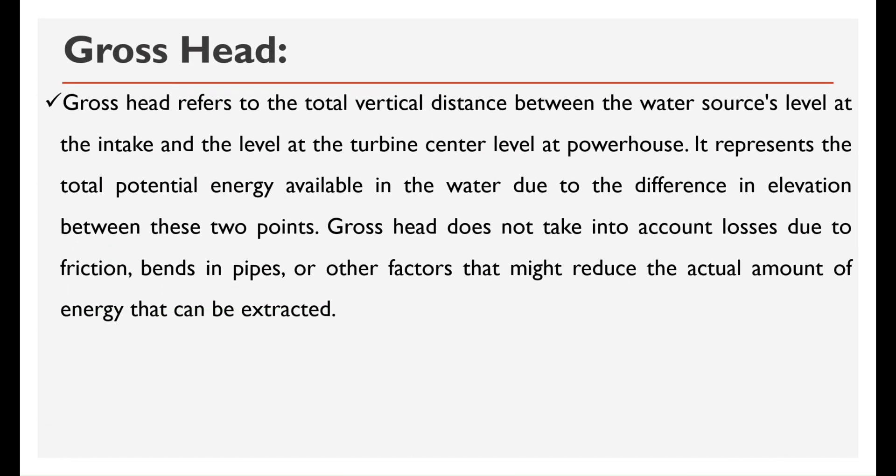Gross head refers to the total vertical distance between the water source's level at the intake and the level at the turbine center level at powerhouse. It represents the total potential energy available in the water due to the difference in elevation between these two points.